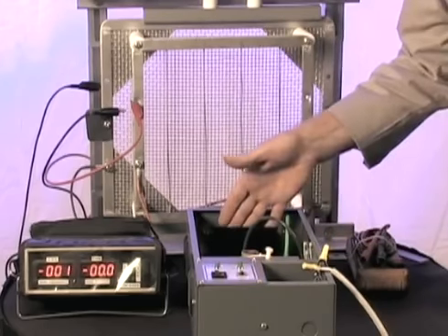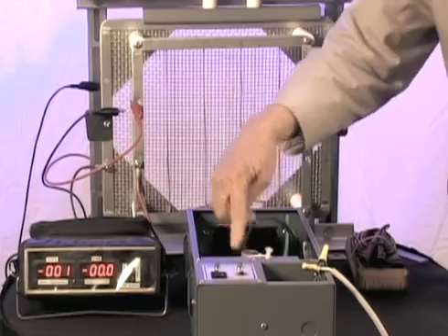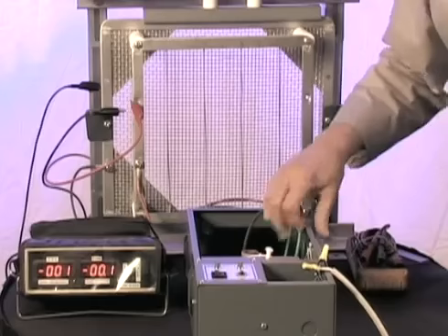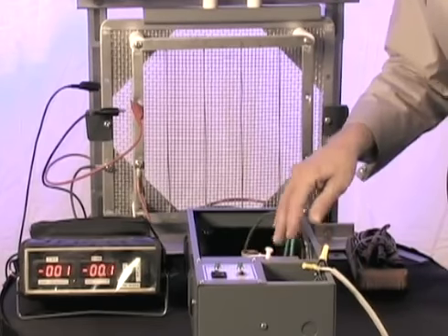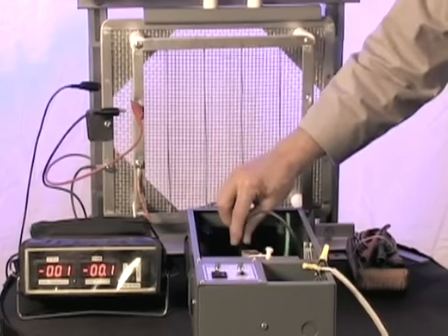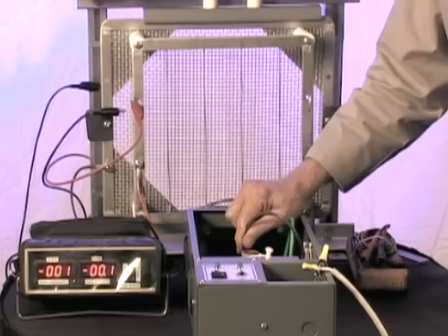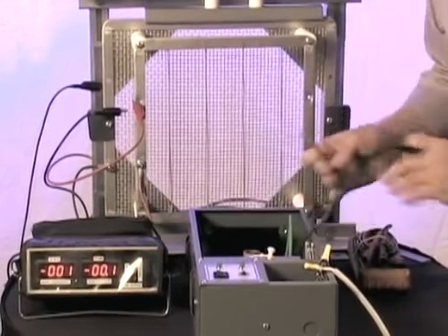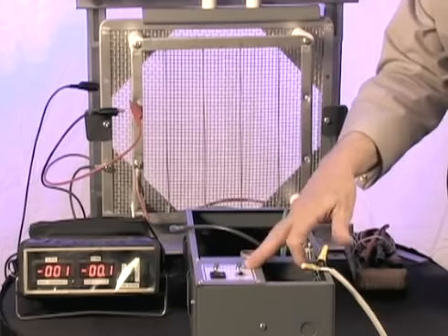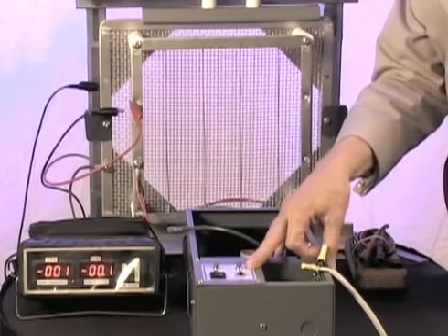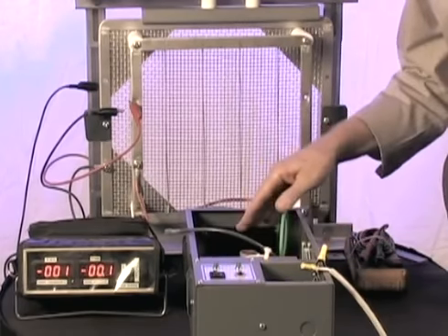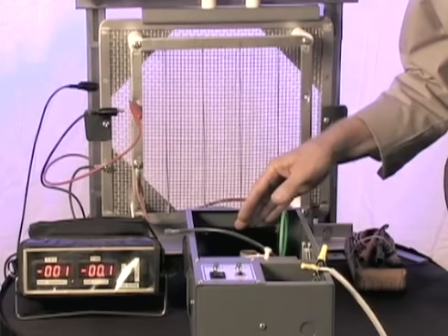If there's a problem with your HF section, with this light out indicating it is a problem, the first thing to look at is the fuse to see if it's okay. If the fuse is still good, but the light is still out, then what you want to do is remove the high frequency wire off the board. This removes the load from the high frequency generator. This should restore the light if the oscillator is still functioning. If the oscillator is not functioning and the fuse is still good, the board is bad and needs to be sent back to CosaTron for repair.